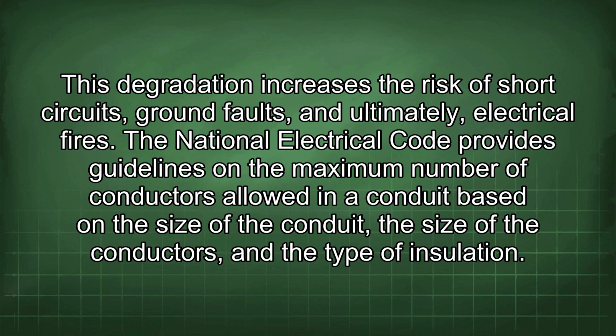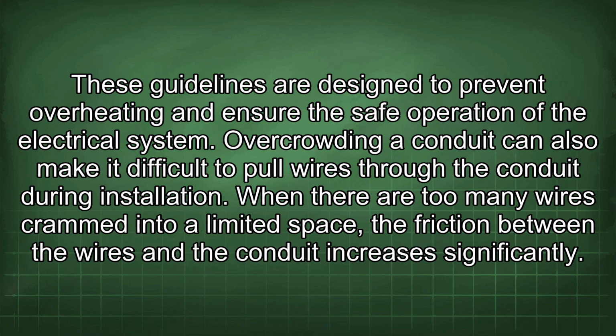The National Electrical Code provides guidelines on the maximum number of conductors allowed in a conduit based on the size of the conduit, the size of the conductors, and the type of insulation. These guidelines are designed to prevent overheating and ensure the safe operation of the electrical system.